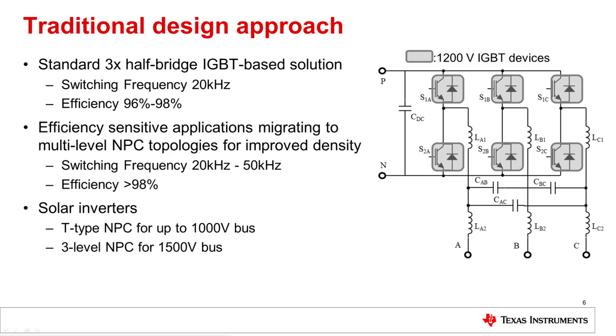In traditional grid tie converters, the power supply is comprised of three IGBT half bridges in a three-phase configuration. The IGBTs are typically in a module package and switch at frequencies up to 20 kHz with efficiencies in the 96 to 98 percent range. This topology is simple to design and has served the industry for many years. As the requirement for higher efficiency and higher density is becoming the norm, grid tie power supplies are migrating to multi-level topologies.